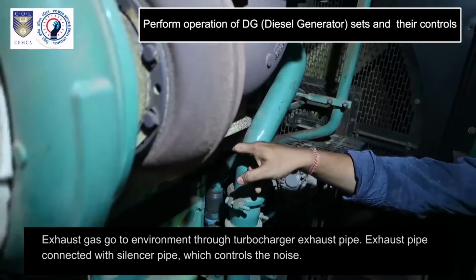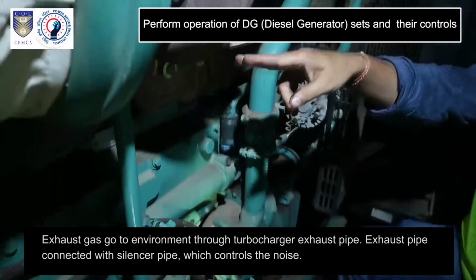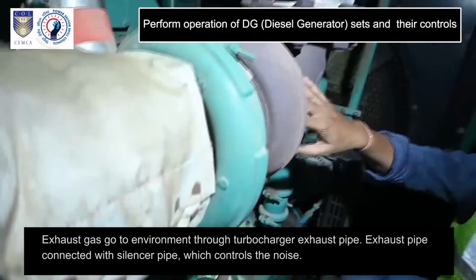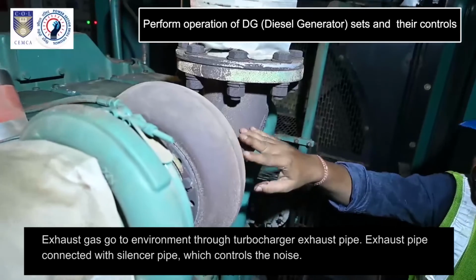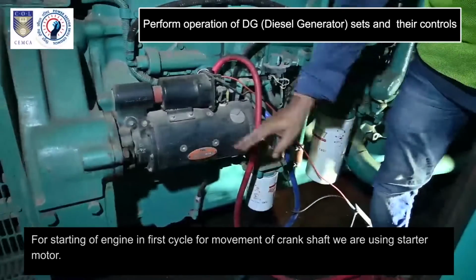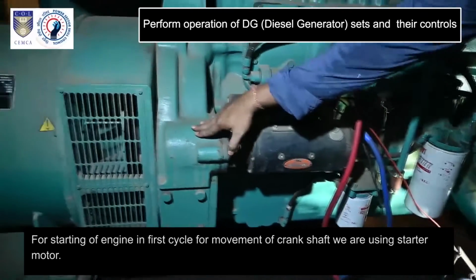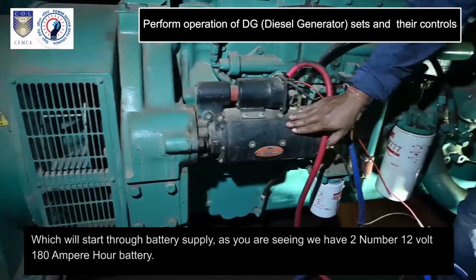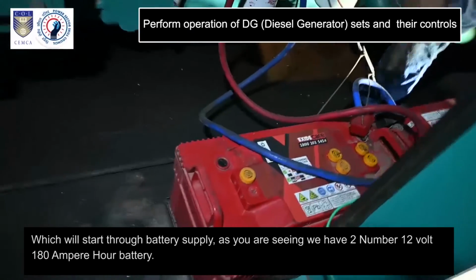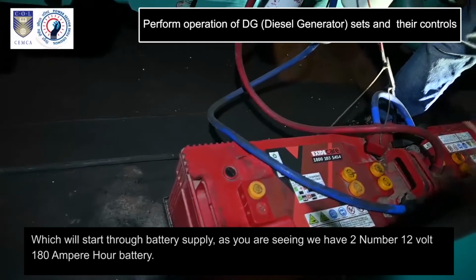Exhaust gas goes to the environment through the turbocharger exhaust pipe. The exhaust pipe is connected with the silencer pipe, which controls the noise. For starting the engine, in the first cycle for movement of the crankshaft, we are using a starter motor, which will start through battery supply. As you are seeing, we have 2 numbers of 12 volt 180 ampere hour batteries.